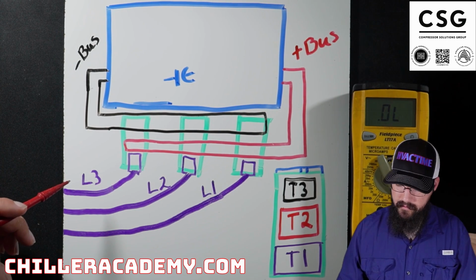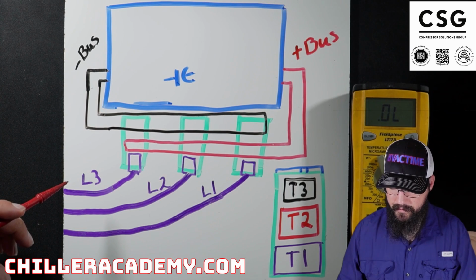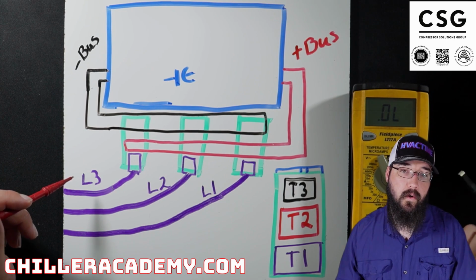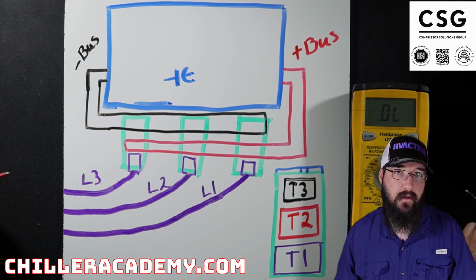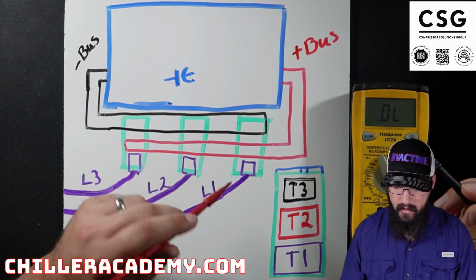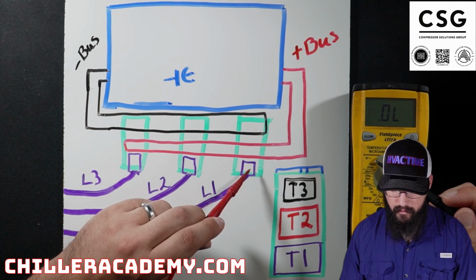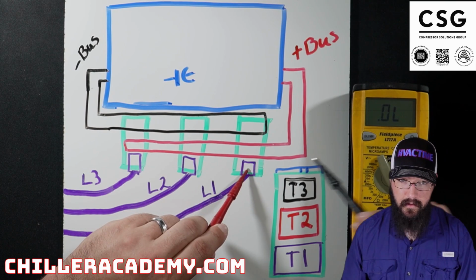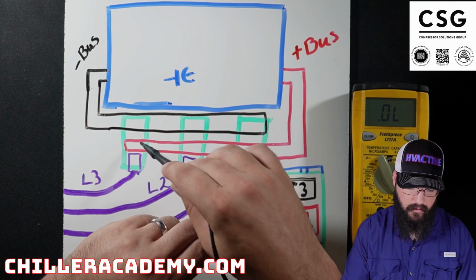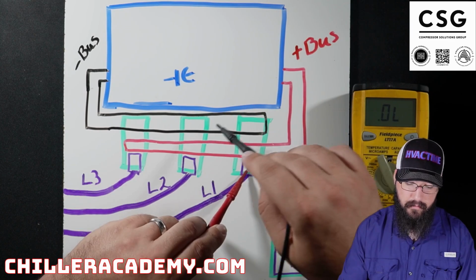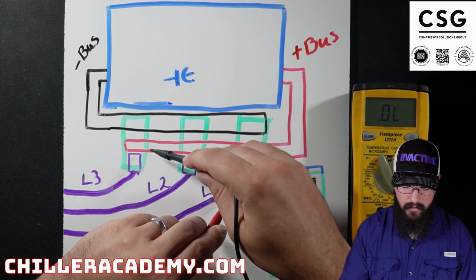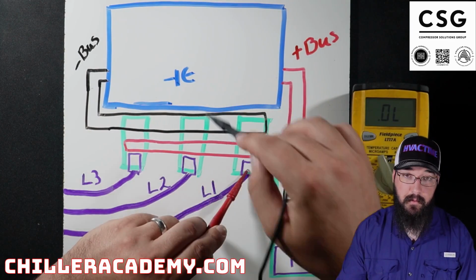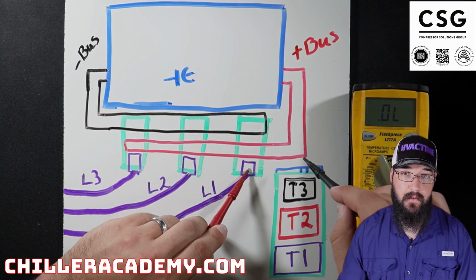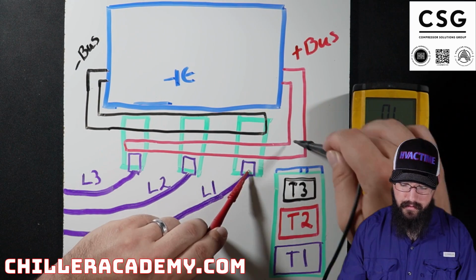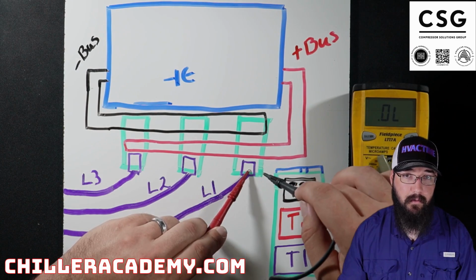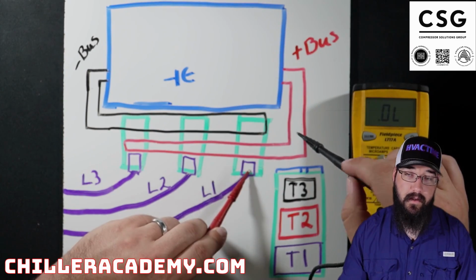So getting into the readings, we're going to have our digital meter set to our diode setting, or if you're using analog, make sure you're just on a X1 scale. The very first test, we're going to put our red lead to our T1 for our SCRs, SCR1, SCR2, SCR3. Right above this is our IGBT assembly, and then these are copper bars that come around and cross over these SCRs. So you could test anywhere you wanted to on these specific bars as long as you're on the correct bus.